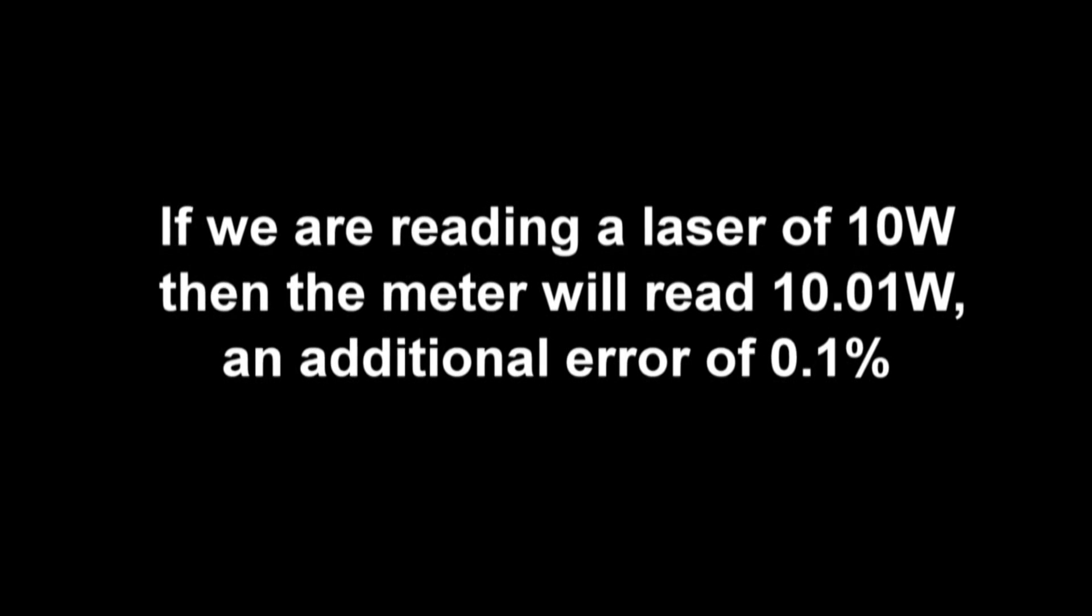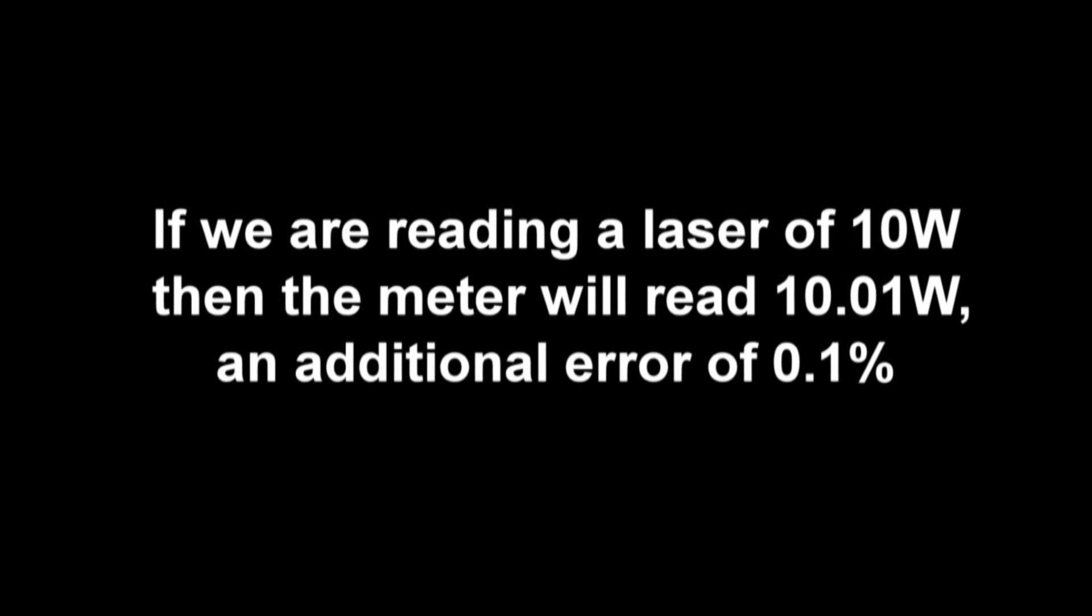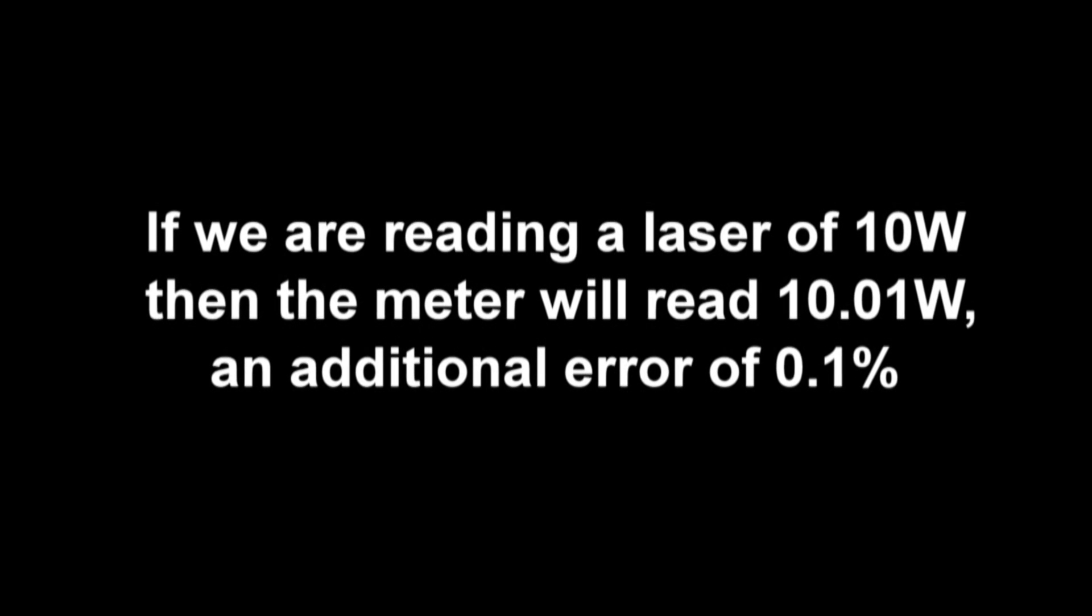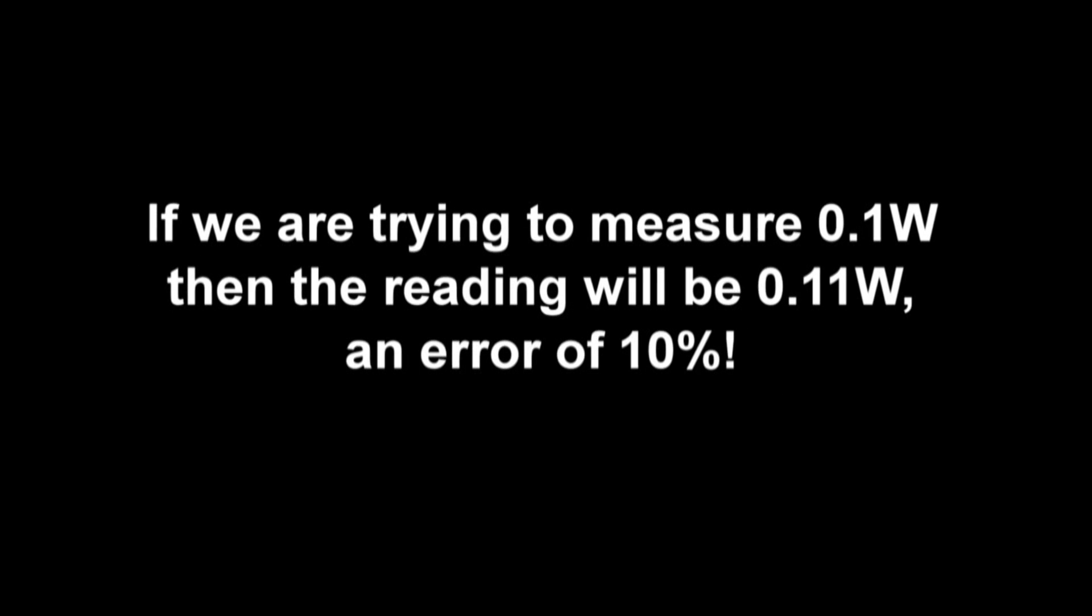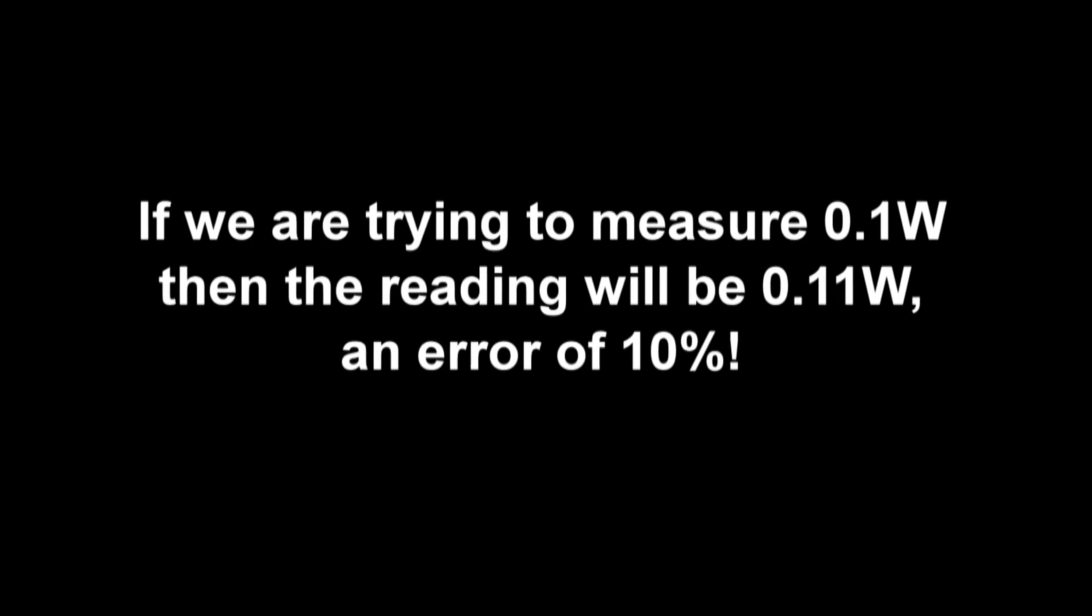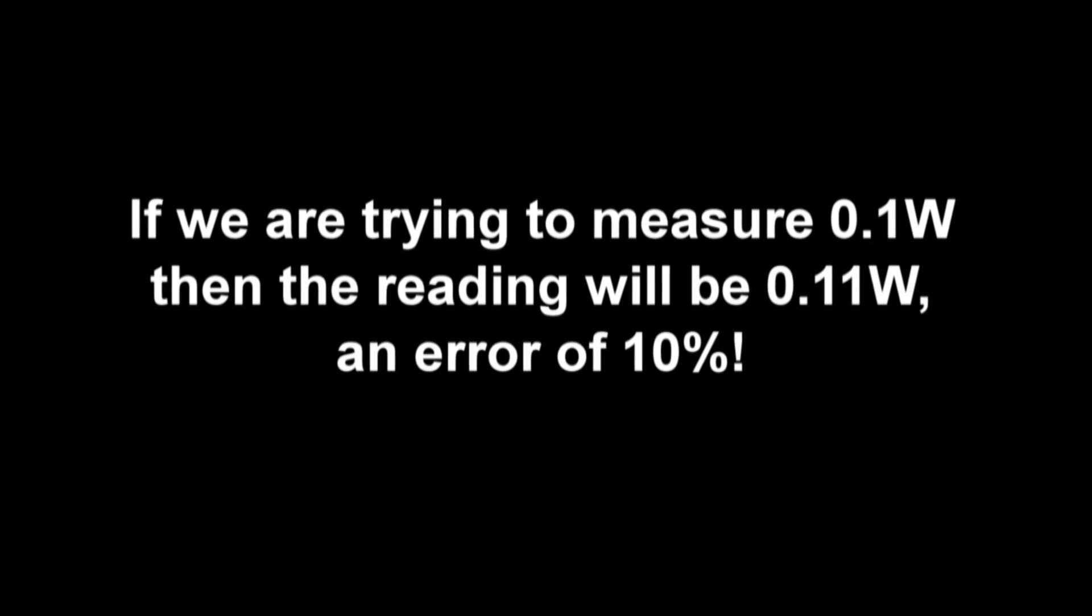If we're reading a laser of 10 watts, then the meter will read 10.01 watts, an additional error of 0.1 percent, very small. But if we're trying to measure 0.1 watt, then the reading will be 0.11 watt, an error of 10 percent.